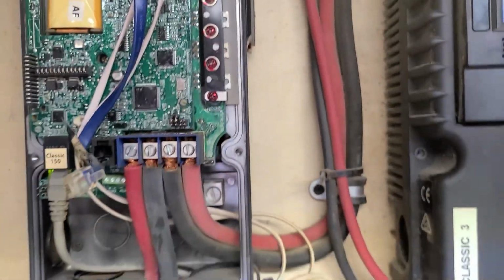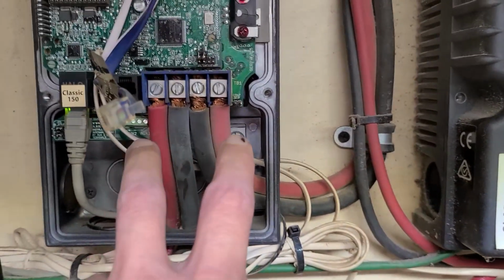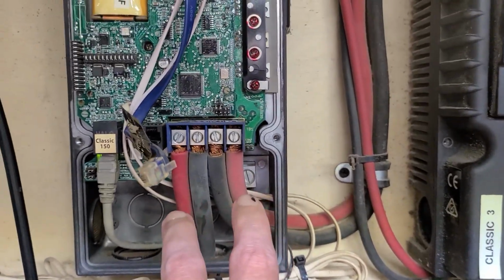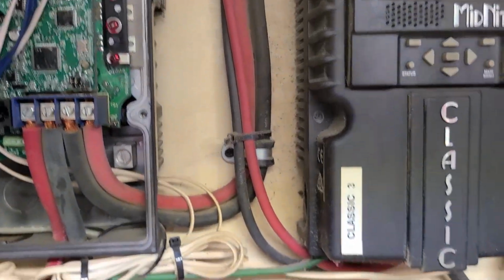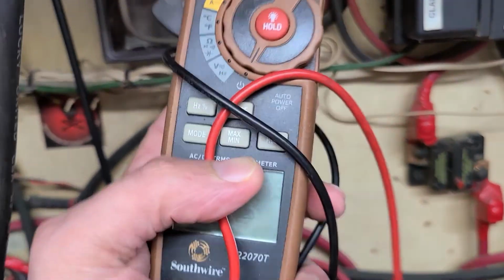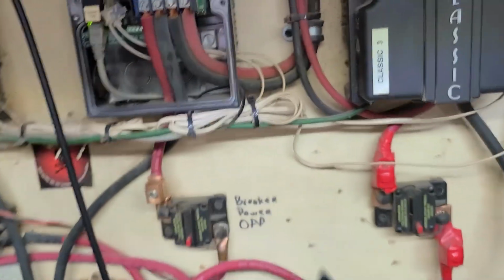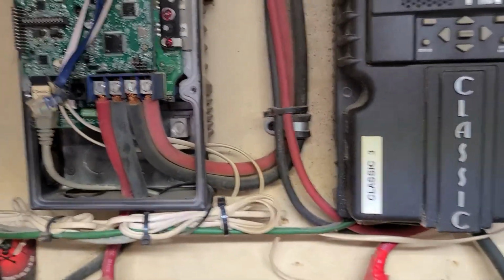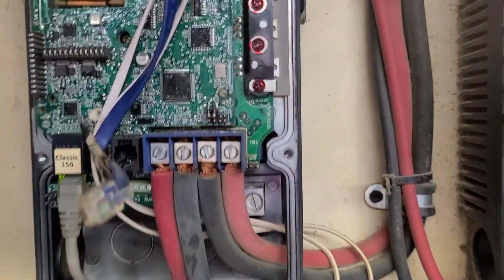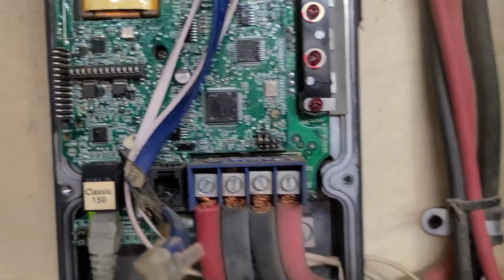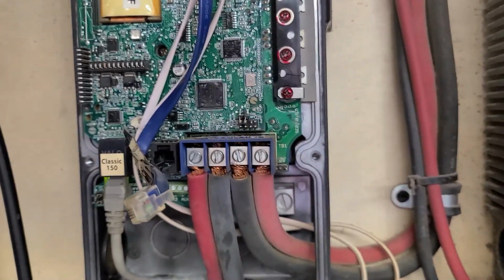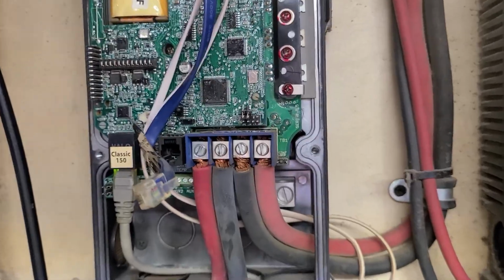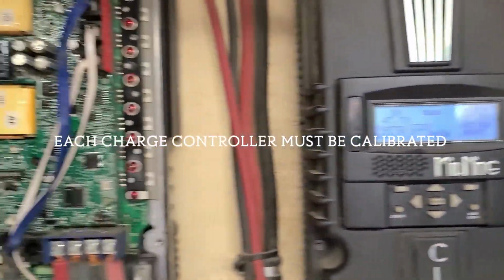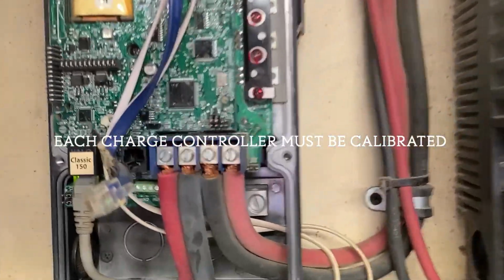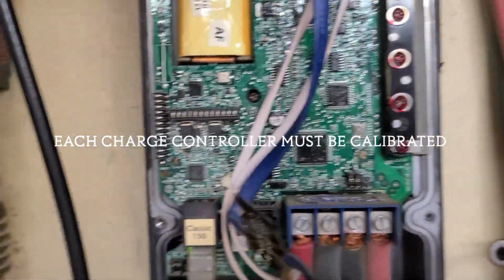What you want to do on your input terminals is put a meter on there, connect it to those terminals, and then adjust this voltage here so it matches what's showing up on your meter. That way you can zero each one of these charge controllers in. Once you do that, you should be golden.